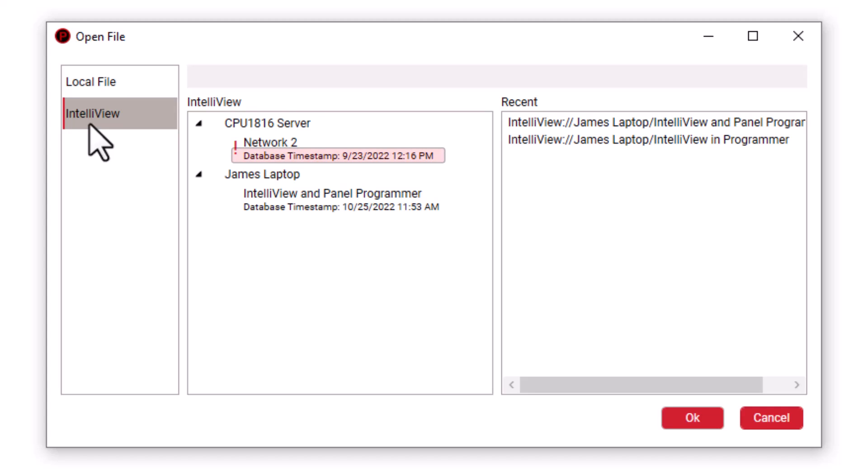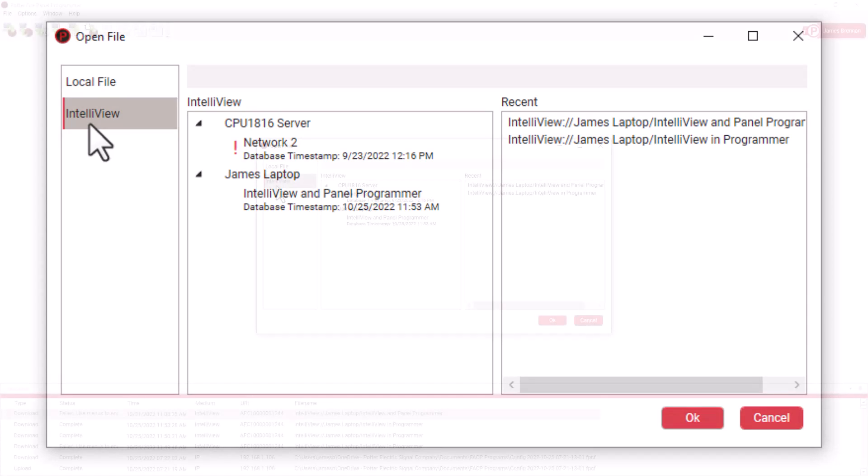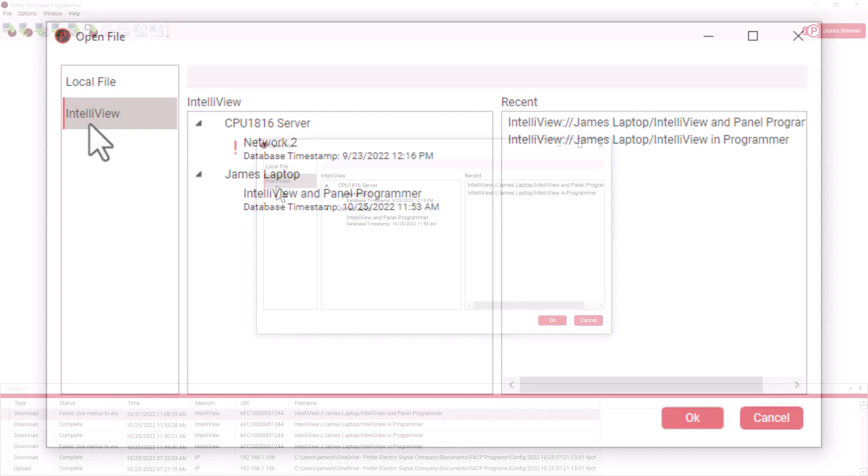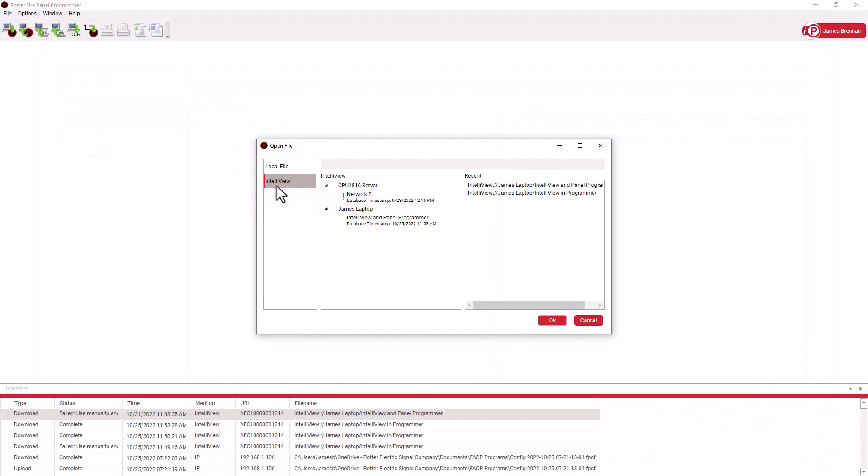Beneath each program entry is a date stamp for when that program was uploaded to the cloud. We can download those to our local machines at any time and edit them. We're not downloading those directly from the panel, but instead from a Potter server that archives the latest program from each IntelliView connected Fire Alarm Control Panel.